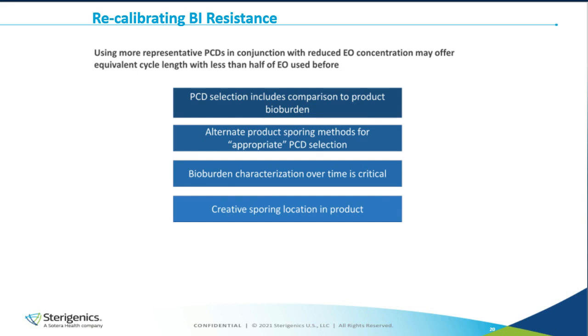To summarize the recalibration of the BI resistance and the PCD selection, we cannot get away from comparing the PCD resistance to the natural bioburden. It is still a requirement, and I encourage all of you to still do that. If we have an alternative method to spore up the devices, we can still meet the 10 to the 6 BI in, I would say, an easier to sterilize location, but that would be more resistant than the worst case location natural bioburden. Bioburden characterization over time remains critical. So it means that if we are basing more of our validation for ethylene oxide on the bioburden, we of course have to have control of that bioburden species and levels. But we can be innovative and create more sporing location in the product, or use a surrogate PCD that would match and exceed the resistance of the bioburden of the devices.